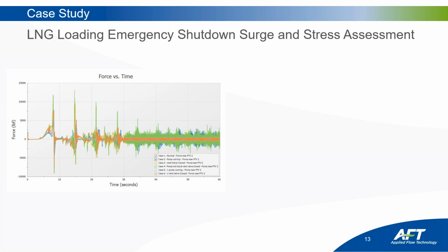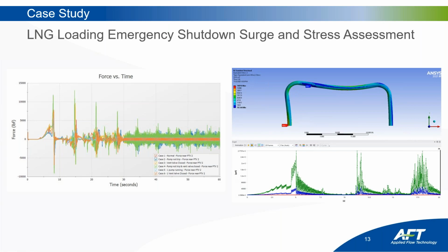From this, they were able to measure the forces as well that were propagating through their system. They were able to see the pressure spikes for the case scenarios and then try to determine more mitigation strategies around it, whether that force was enough to break things or not. You would need to determine for yourself, but it would be able to tell you a force over time, within a certain pipe, on a scenario basis, etc.